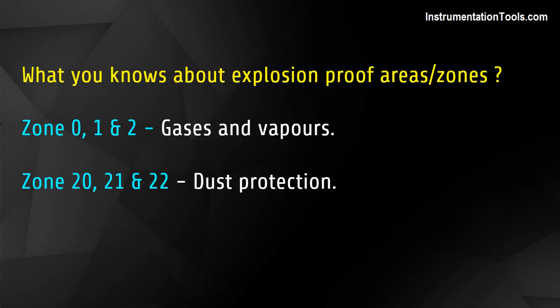What do you know about explosion-proof areas and zones? Zones 0, 1, and 2 are for gases and vapors. Zones 20, 21, and 22 are for dust protection.